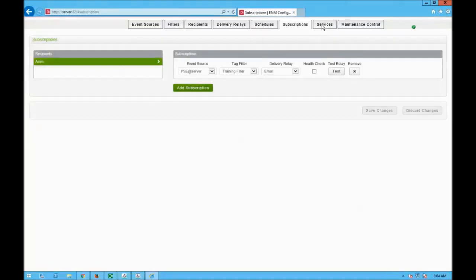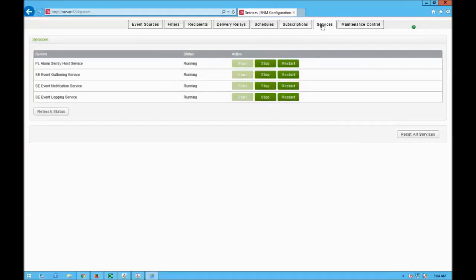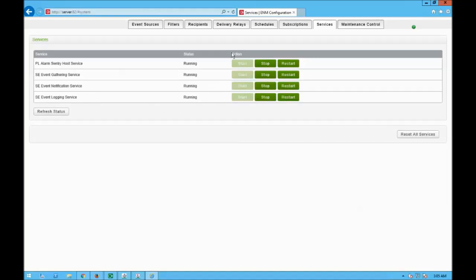I go to services and make sure all services are running: the alarm sentry, event gathering, event notification service, and event logging service. If any are not running, I can restart, start, or stop them from here.